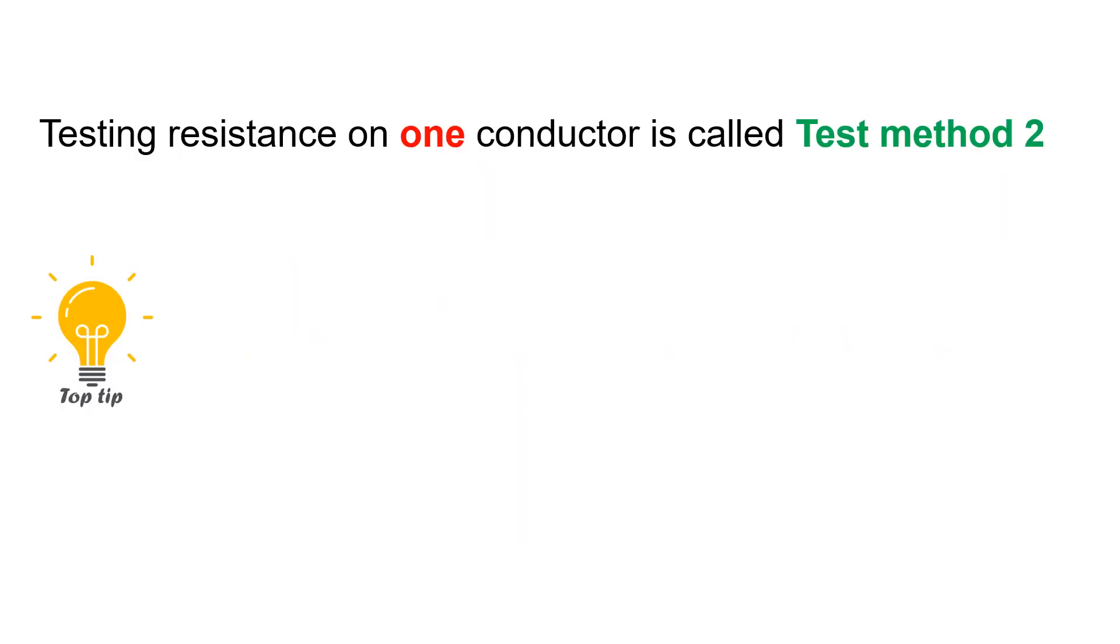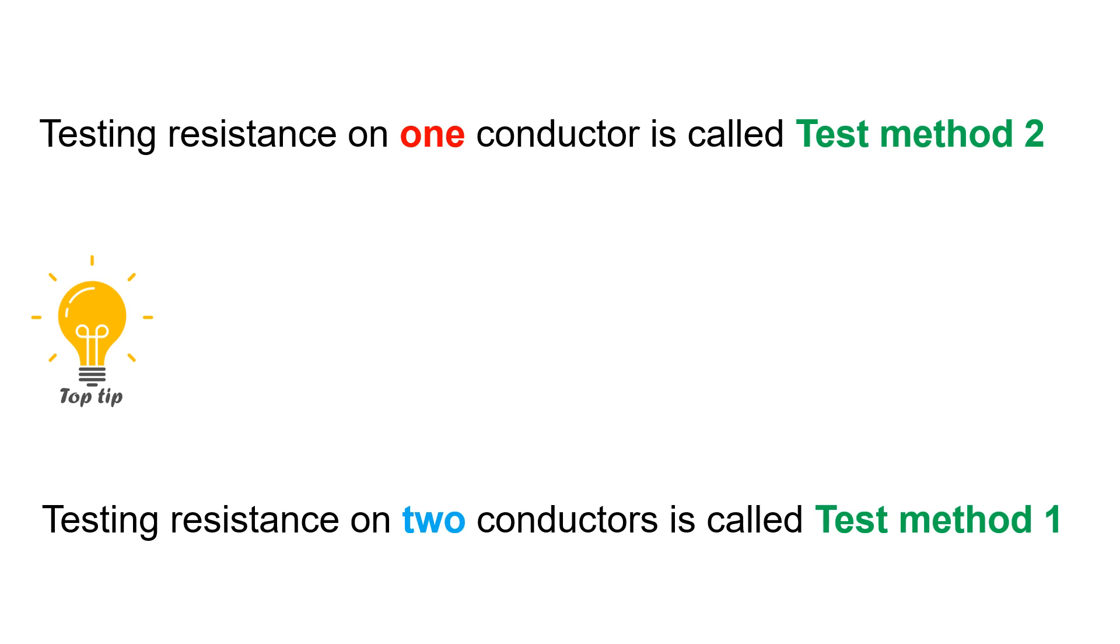Just to be clear, when you are testing one conductor like the CPC, that is called test method two. But when you are testing two conductors like your line and CPC together, that is called test method one. Pretty confusing, don't you think? Surely the IET would have identified those test methods the other way around to make it easier to remember. It would make more sense that testing one conductor would be test method one and testing two conductors would be test method two. Much easier. But for now, this is what we are stuck with, and you will have to do your best to remember that they are the opposite way around.